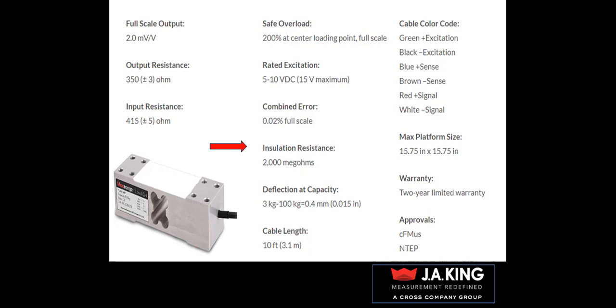The insulation resistance. This is for testing for moisture ingress, and you must have a mega ohm meter for testing this resistance. And if listed, a zero balance spec. Not all cells list a zero balance spec.